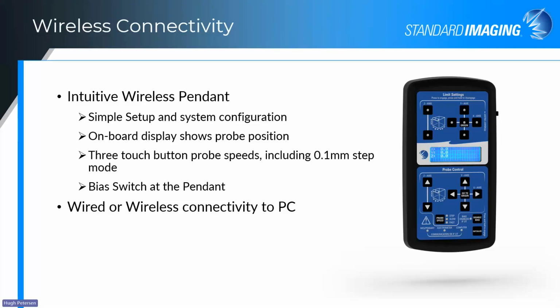And then we also have the ability included with the system to be either wired or wireless. We include a radio receiver and transceiver system for wireless scanning. It's typically from the inside wall of the LINAC, where the receiver would be, going to the transceiver on the motion control unit of the tank itself. That gives you the ability to do those scans wirelessly from there.